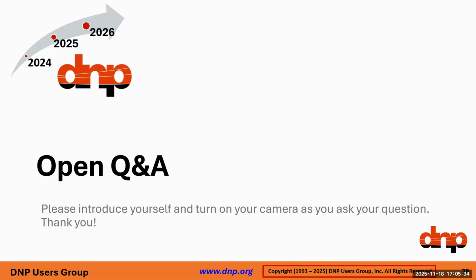With 2030.5, I think it's pretty complete. Everything is supported through device and service discovery, and all of the information elements are self-describing, so you can dynamically learn the support of a device. Just taking DER as an example, because 2030.5, like DNP, addresses a lot more than just DER—but using DER as an example, it's everything from the settings and nameplate ratings to a way to describe which are supported, a way to describe the control modes that are supported, and a way to identify all the different reading types supported for metering or metrology-type readings. With a given server, you can do all sorts of service discovery. So quite a lot of work went into 2030.5 when it comes to device discovery, service discovery, and self-describing information elements.